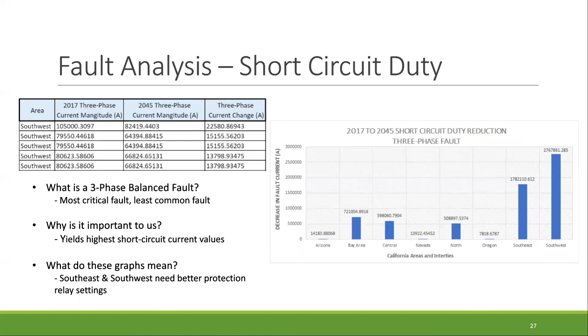As a result, the California areas southeast and southwest have total reductions of 1.7 megaamps and 2.7 megaamps. Short circuit analysis showed a decreased fault current in areas where the gas resources were mostly retired. This is why the southeast and southwest have the most reduction. Because of our analysis, we recommend further evaluation of the protection settings for both of those areas.